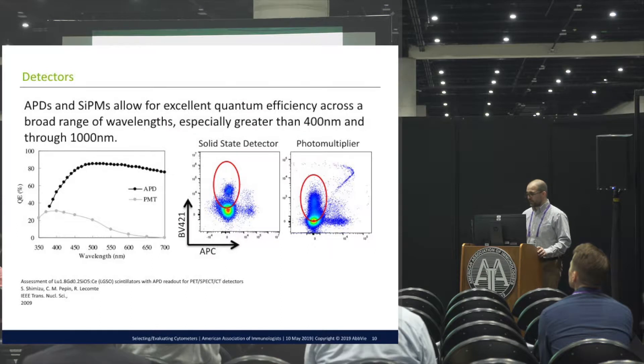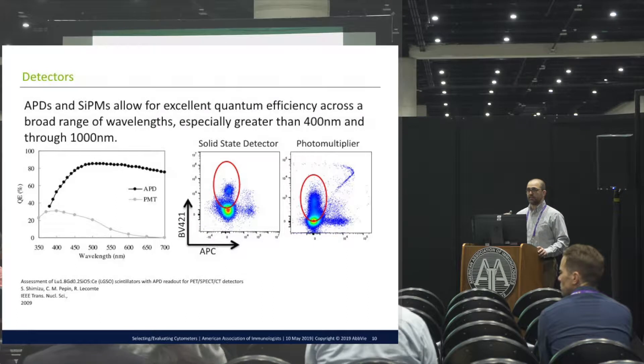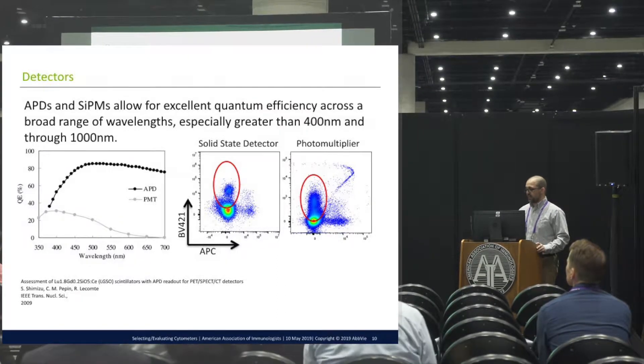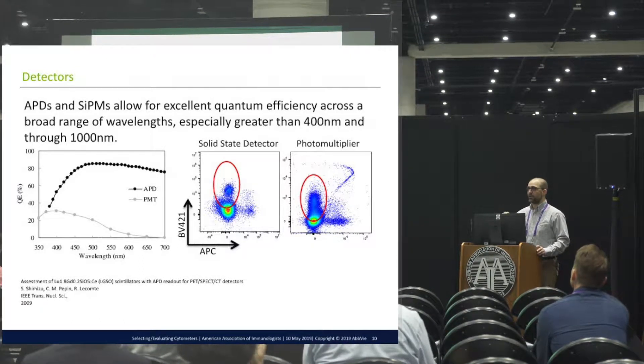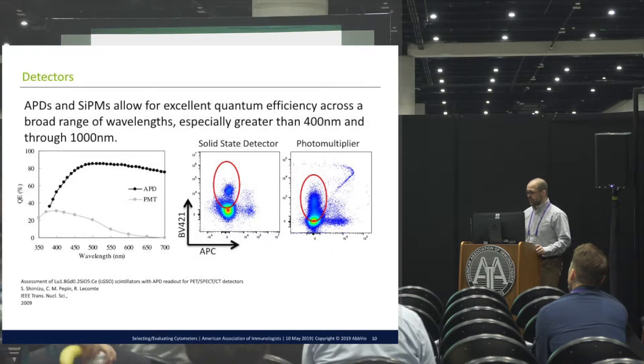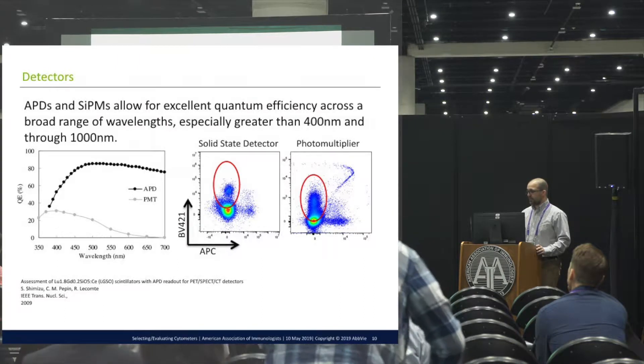PMTs can convert shorter wavelength photons pretty well, but especially when you get into the further red region, that's where PMTs suffer in terms of quantum efficiency. Whereas APDs have the unique characteristic of having really good quantum efficiency all the way out to the very far red range, even into the near-infrared. At the very low end they suffer a little from very low wavelengths, but for high-wavelength, low-energy photons they do a really good job, which translates into better resolution.